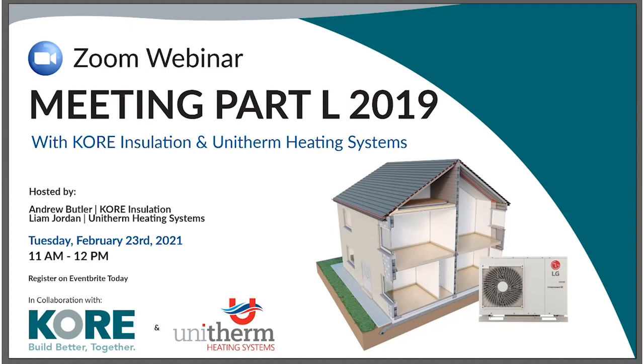If you want to send me an email to Liam@UnithermHS, I can give you the exact figures, the seasonal COPs for all our units in-house - Hitachi, Daikin, LG, the comfort zone exhaust. I have them all readily available. But the difference in the COP, the LG Therma V monoblock has higher seasonal COPs than any other monoblock counterpart. As I said, it's the world's first R32 monoblock, and it utilizes enhanced vapor injection, which gives it higher enthalpy values on the thermodynamic cycle.